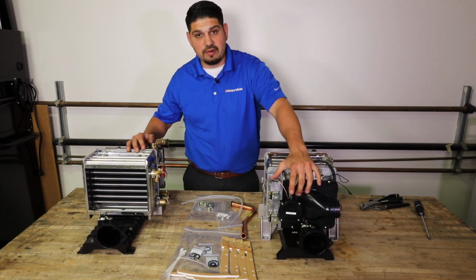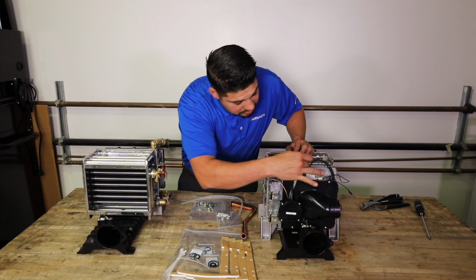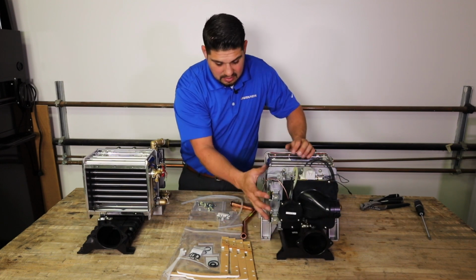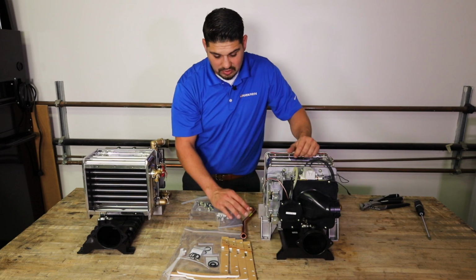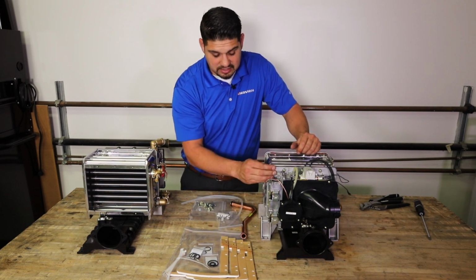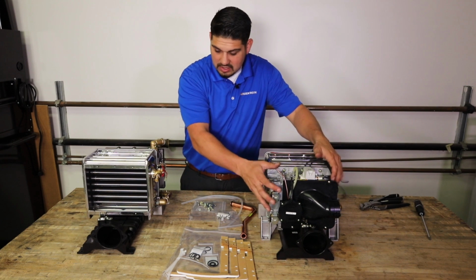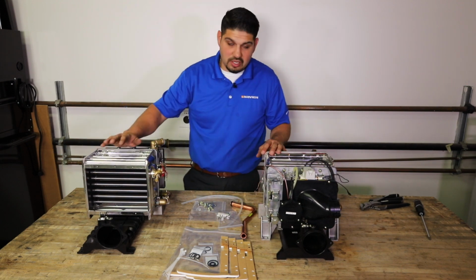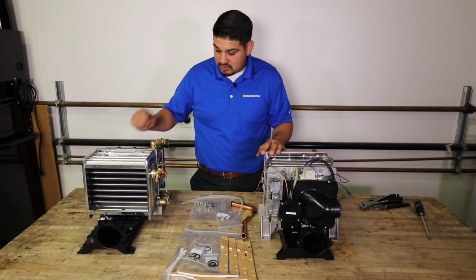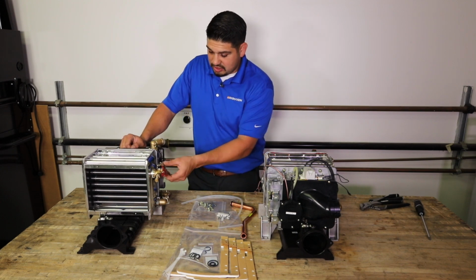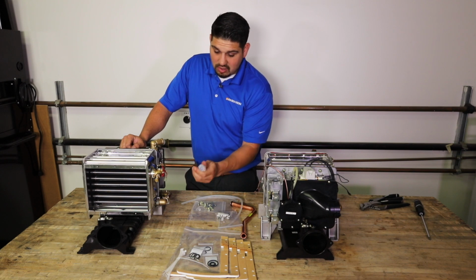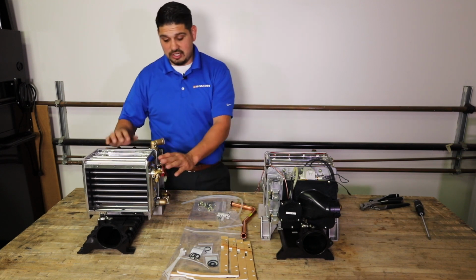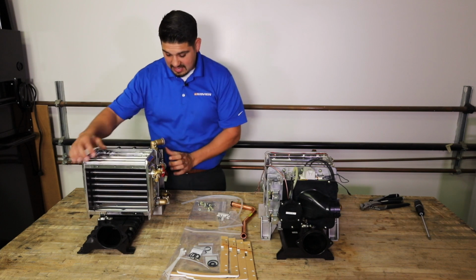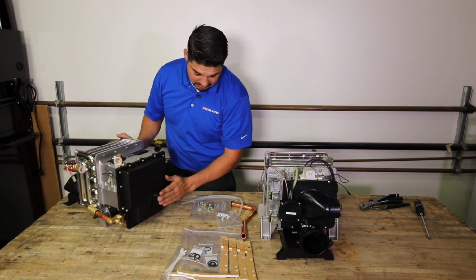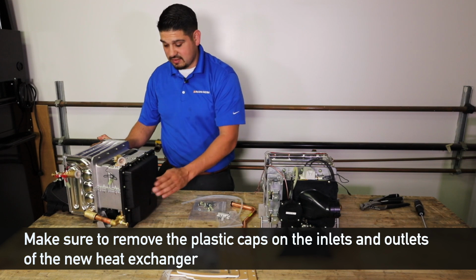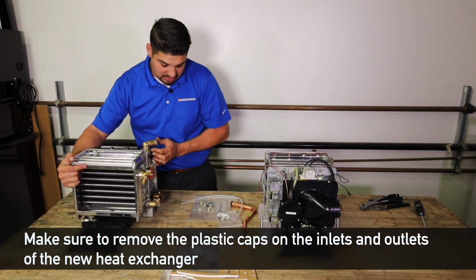And what we're going to have to do here is take off this burner assembly. And there's 1, 2, 3 screws here, another 3 along the back. This whole burner assembly is going to come off. We're going to clean off these gaskets that are attached to it, clean those off to the best of our ability. Put that new burner assembly on the new heat exchanger, bolt it back up, and just put this one right back in the cabinet. Just be careful and remember on all the inlets and outlets of our new heat exchanger, you're going to have these caps as well. Doesn't really have it here, but some of them will have a cap on the condensate, so don't forget to take off those caps or you can have an issue there.